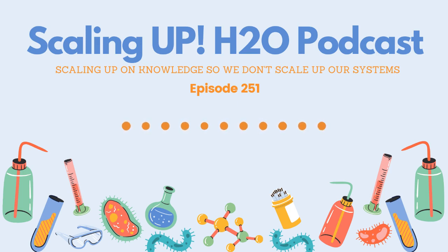Every time water concentrates, the conductivity goes up, and also everything concentrates that you put in that machine. If it's not concentrating up, you're going to see the conductivity at a lower range than what you have it set for, and that's going to indicate that one or all of your parameters that you're going to check for are going to be low.